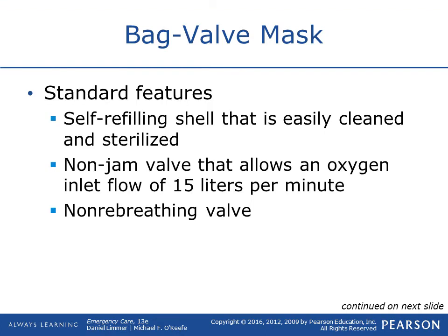The design of a BVM, it's pretty basic. As you squeeze the bag, that material refills itself. So as you squeeze, it's going to fill back up with air, re-expand, and then you're going to squeeze it again the next time when it fills back up. The one-way valve is a non-rebreathing valve, so that if something did come up through the patient's mouth, it's not going to interfere with the process. It's not going to jam up that valve. It's not going to clog it up or get into the bag to where you basically have something in the bag and can squeeze it out as a projectile. It's just that one-way valve.